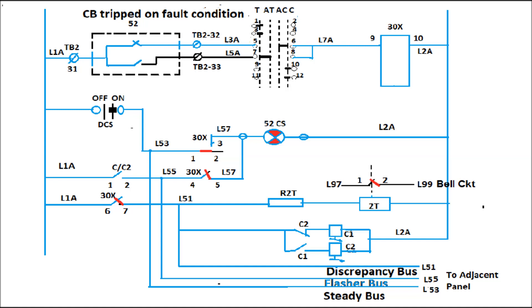The discrepancy circuit after CB tripped has been shown in this figure. As previously CB was closed and CB remained in closed position, due to CB tripped on fault condition, the discrepancy has occurred through auxiliary contact of CB and discrepancy relay. Therefore, discrepancy bus and flasher bus will be energized as shown in this figure.